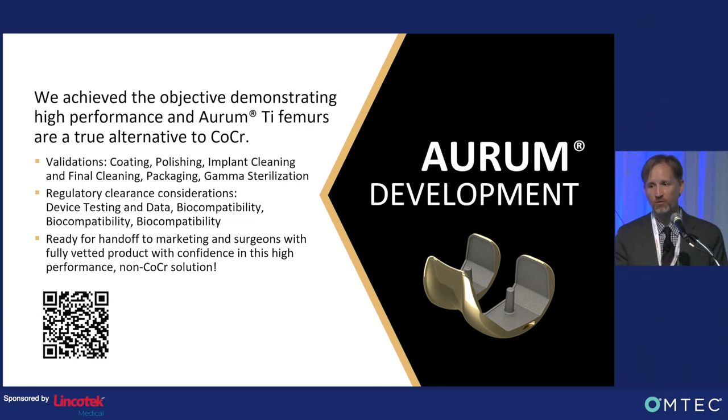With that, also moving into regulatory clearance for the device, testing specific to the femoral geometry, as well as the testing that you've seen. And then I've written biocompatibility three times here because I can't stress the importance of this consideration for a new material in the marketplace.